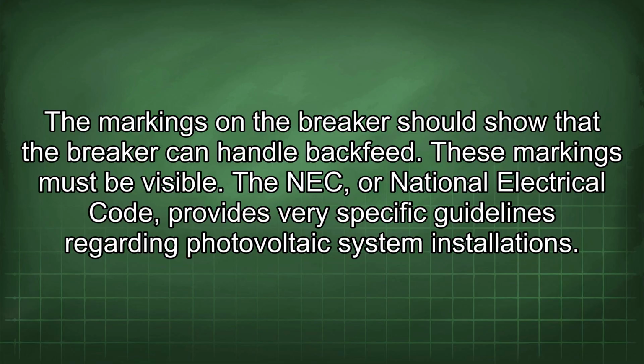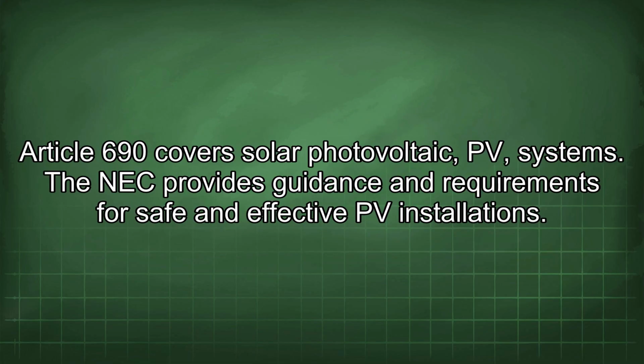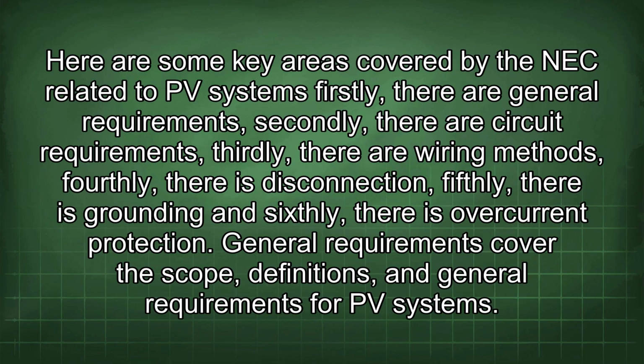The NEC, or National Electrical Code, provides very specific guidelines regarding photovoltaic system installations. Article 690 covers solar photovoltaic (PV) systems. The NEC provides guidance and requirements for safe and effective PV installations. Here are some key areas covered by the NEC related to PV systems. Firstly, there are general requirements. Secondly, there are circuit requirements. Thirdly, there are wiring methods. Fourthly, there is disconnection. Fifthly, there is grounding. And sixthly, there is overcurrent protection.